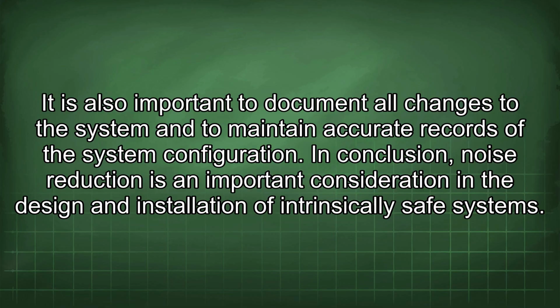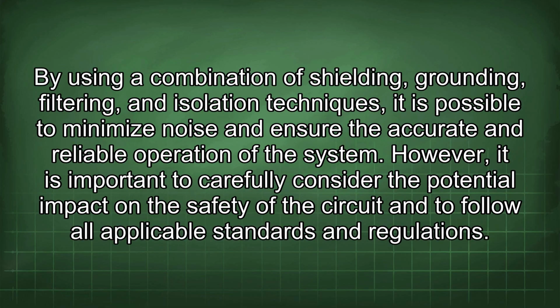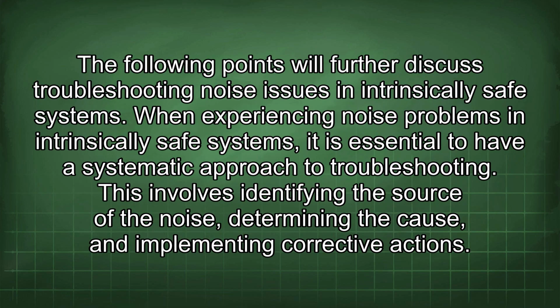of the system configuration. In conclusion, noise reduction is an important consideration in the design and installation of intrinsically safe systems. By using a combination of shielding, grounding, filtering, and isolation techniques, it is possible to minimize noise and ensure the accurate and reliable operation of the system. However, it is important to carefully consider the potential impact on the safety of the circuit and to follow all applicable standards and regulations. The following points will further discuss troubleshooting noise issues in intrinsically safe systems.